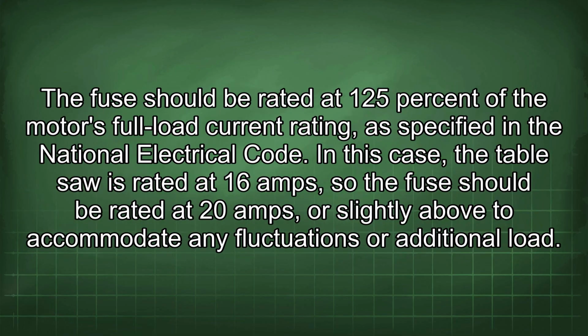The fuse should be rated at 125% of the motor's full load current rating, as specified in the National Electrical Code. In this case, the table saw is rated at 16 amps, so the fuse should be rated at 20 amps, or slightly above to accommodate any fluctuations or additional load.